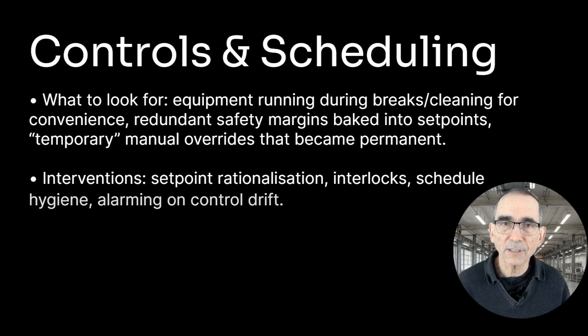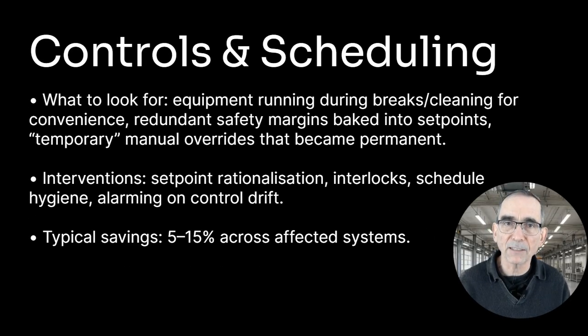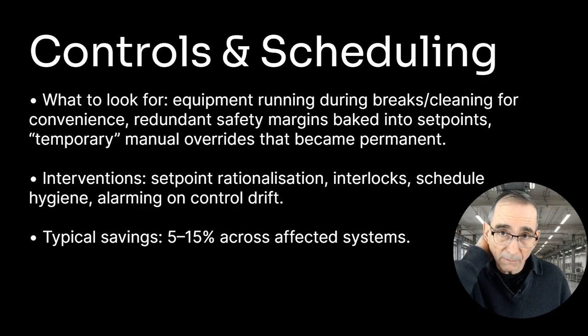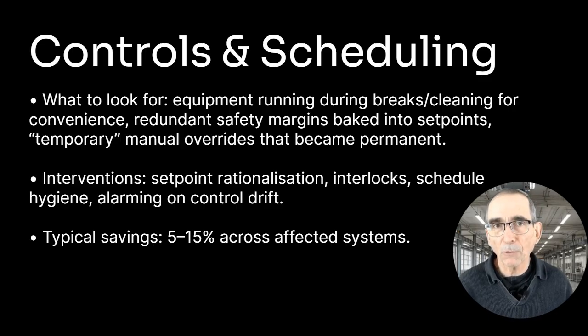Then we look at controls and scheduling. You can look for equipment running during breaks, cleaning, just for convenience, operating overnight, operating on weekends, redundant safety margins put into set points, temporary manual overrides that become permanent. And interventions here can be set point rationalization, interlocks, improved I'm a big fan of manual on, auto off control, scheduling of cleaning and hygiene to keep equipment in good condition, alarming on control drifts. So savings might be in the range of 5 to 15%. So these are just, again, indicative savings, maybe high, possibly a little bit higher.